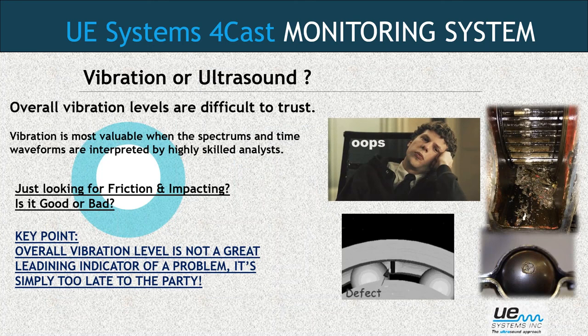So really what that means is that just taking an overall vibration level from a piece of rotating equipment is not the best method. The overall vibe levels are just difficult to trust. Vibration really works well when you've completely analyzed the spectrum. So it takes some skilled observation. It takes someone who understands the waveforms, the FFT and the time waveforms to be able to interpret that data. So typically that's a highly skilled analyst.